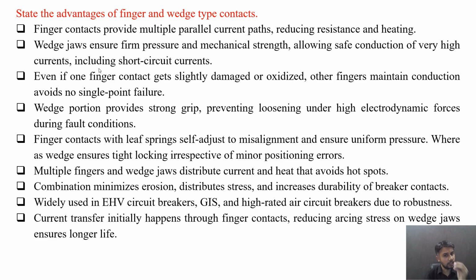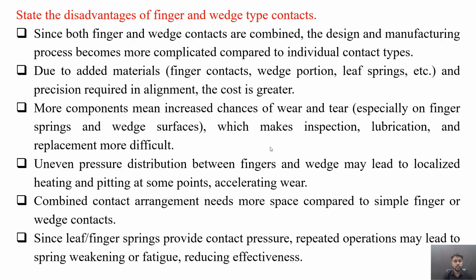The combination minimizes erosion, distributes stress and increases the durability of breaker contacts. It is widely used in EHV circuit breakers, GIS, and high-rated air circuit breakers due to its robustness. Current transfer initially happens through the finger contacts, reducing arcing stress on the wedge jaws and ensuring longer life. So these are several advantages of finger and wedge type contacts.